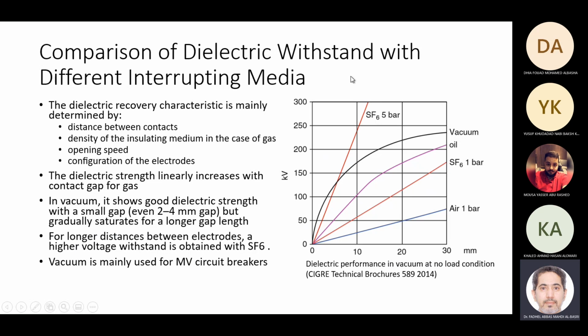Their dielectric properties get better. In vacuum, they have very good properties at short distances. As you can see, even with a 2 to 4 millimeter gap, they have better dielectric properties than SF6. So like here, up to 2-3 millimeter, I have 100 kV dielectric properties. So I can use this for medium voltage applications with a small gap. A small gap will help to reduce the size of the breaker.